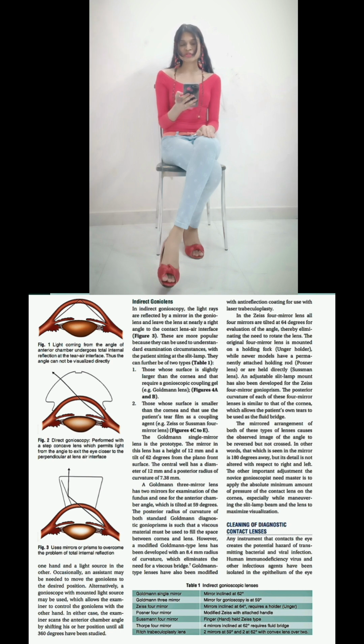However, a modified Goldmann type lens has been developed with an 8.4 mm radius of curvature, which eliminates the need for a viscous bridge. Goldmann type lenses have also been modified with anti-reflection coating for use with laser trabeculoplasty.